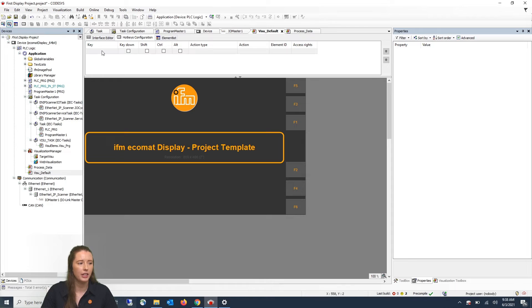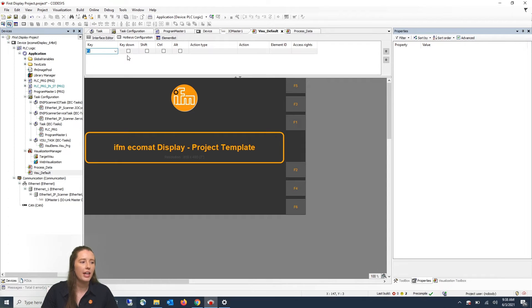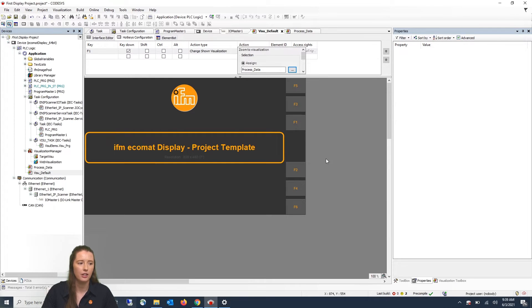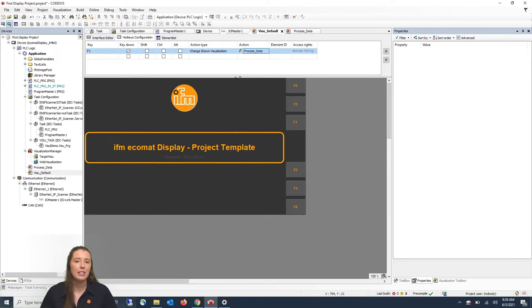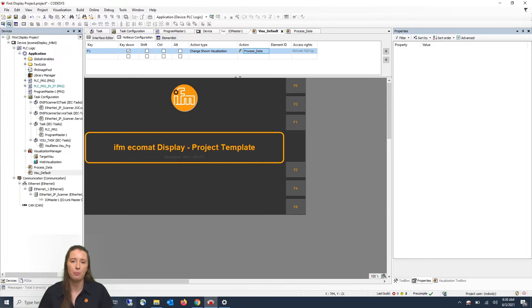If you double-click on the Key column you will see a drop-down appear. For this example I'm going to click on the F1 button. You will then select Key Down, and you can select Action Type — another drop-down will appear and we are going to select Change Shown Visualization. Then in the action you can click on the three dots to the right of the Assign field, and we are going to select Process Data and press OK and press Enter. This means when we click on the F1 hotkey button to the right of the CR display, it will take us to our PI process data that we set up in the previous visualization.